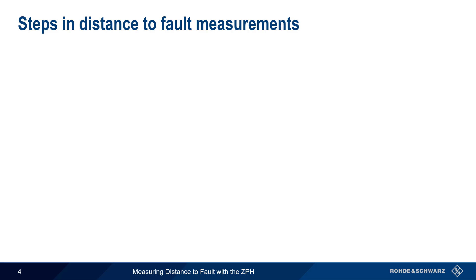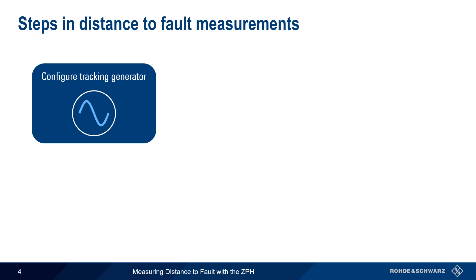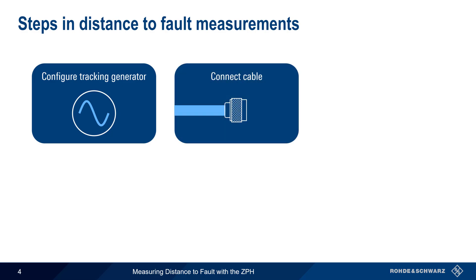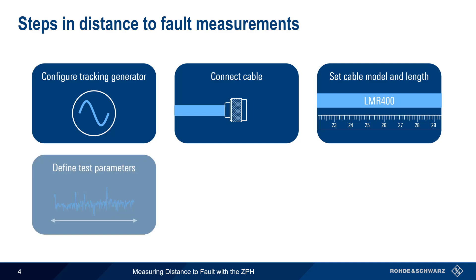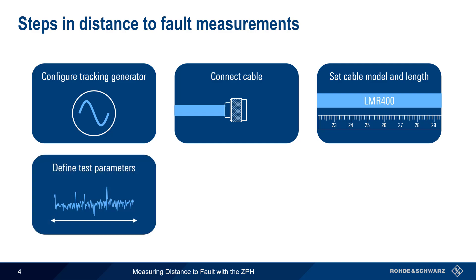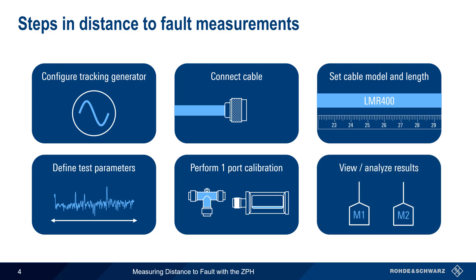There are six basic steps in making distance to fault measurements: configuring the tracking generator, connecting the cable, setting the cable model and length, defining the measurement parameters, performing a one-port calibration, and viewing and/or analyzing the results. In the remainder of this presentation, we'll go through each of these step by step.